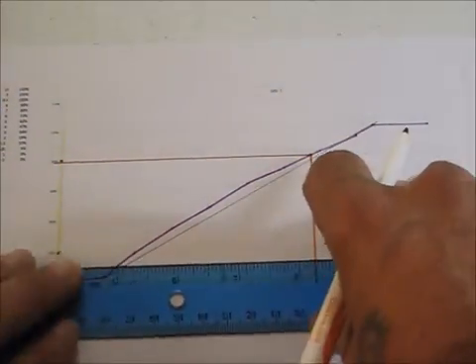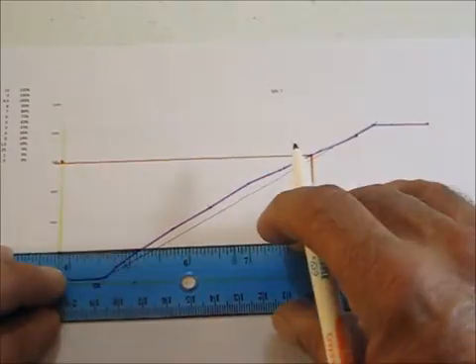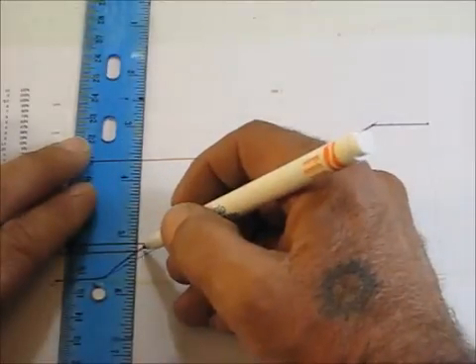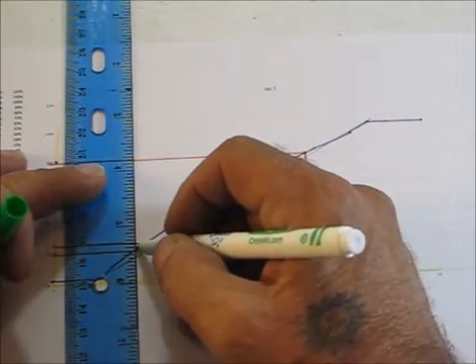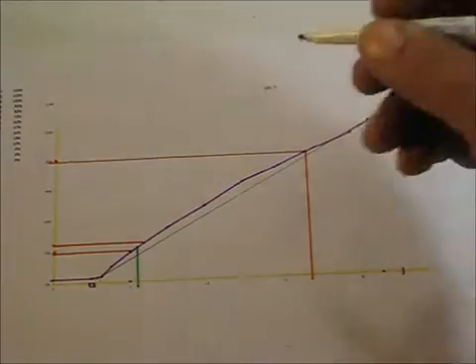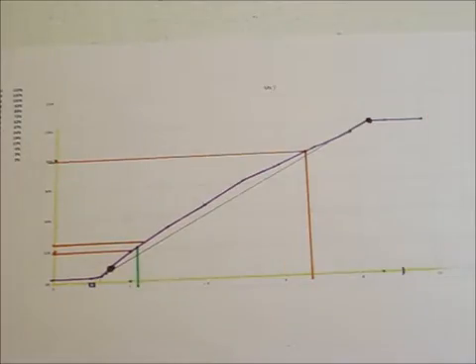He is the best, thanks Mr. Rundgren. So, there's 80%, and then once again, we're interested at 20 to 25% for the bottom end of daylighting. And you can practically use a straight line approximation between these two points to set up a controller between here at about 8.5 volts and here at about 1.5 volts. Excellent. Absolutely excellent.